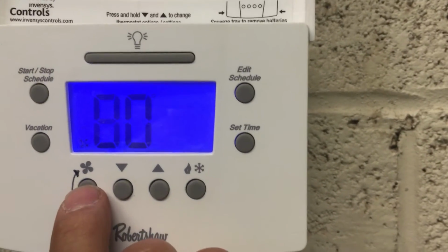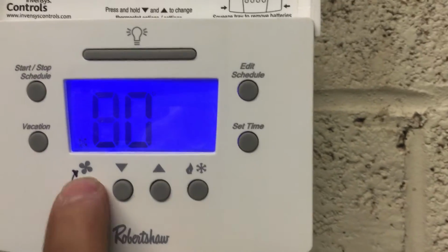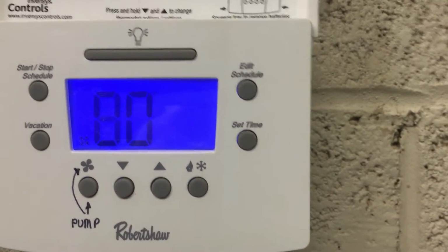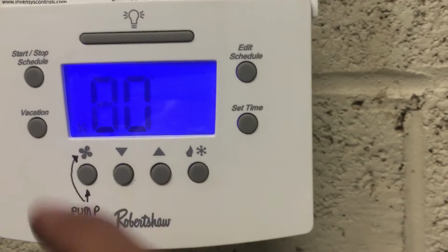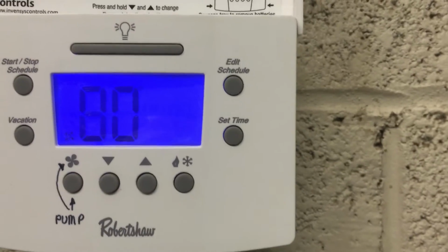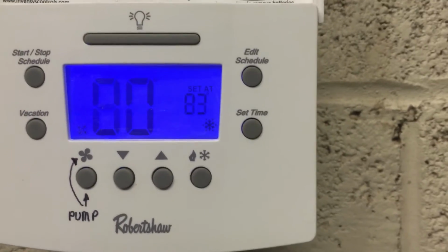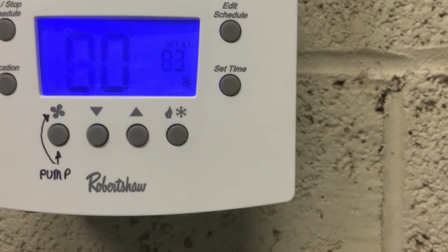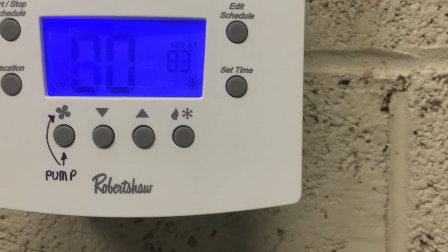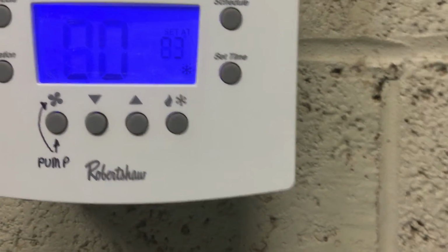We can turn it on where it'll be on consistently. You could have it in circulate or auto. The default mode we want it in is always auto. If it's on, obviously it'll be on all the time. In circulation mode, the fan is gonna cycle. Every 10 minutes it'll be on, off for 20 minutes. You do not want that. It'll cause a lot of intermittent issues with your pump turning on and off.